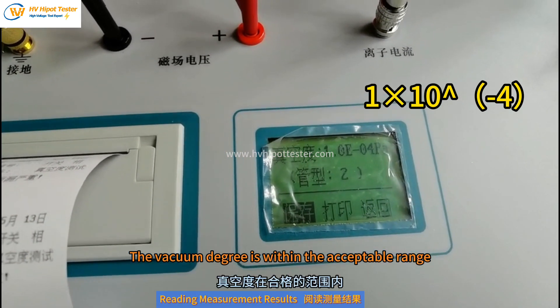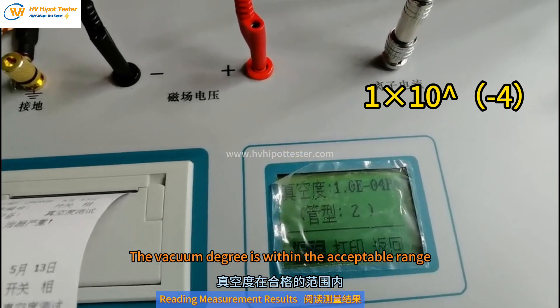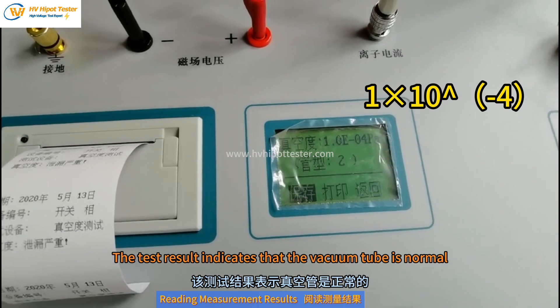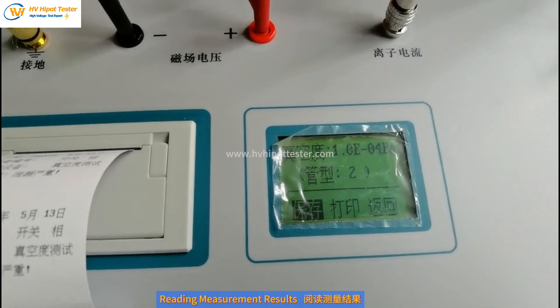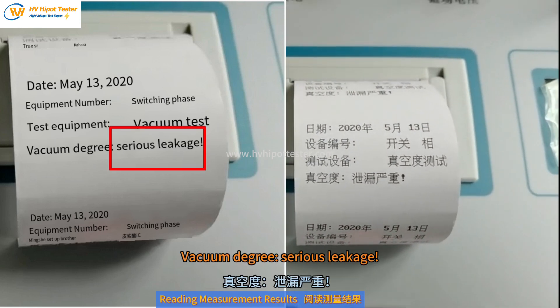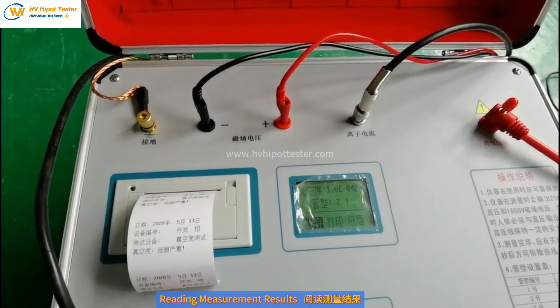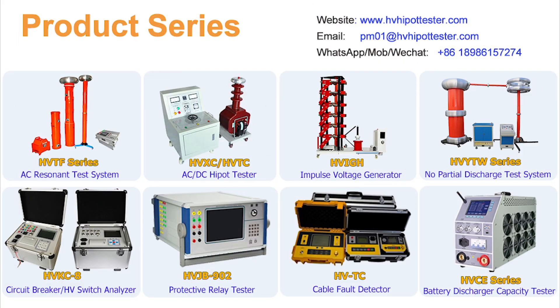The vacuum degree is within the acceptable range. The test result indicates that the vacuum tube is normal. If there is a problem with the vacuum tube — such as a vacuum bubble or serious leakage — this indication line will appear in the test results. That is all for this presentation. Thank you for watching the tutorial video prepared by HV Hipot Tester.